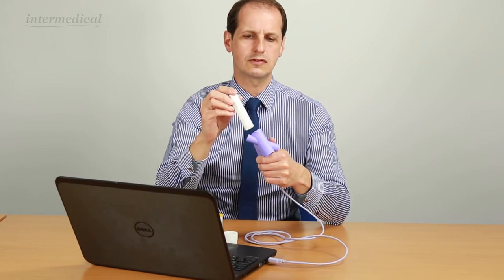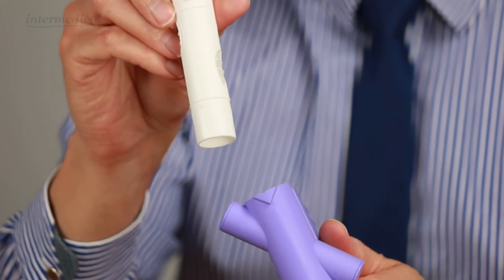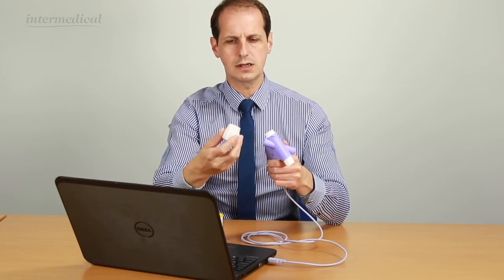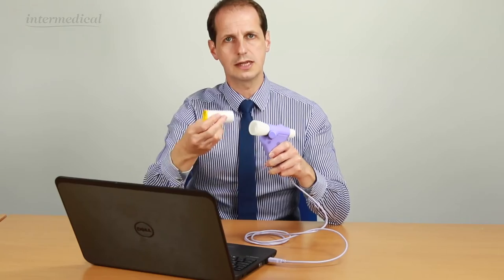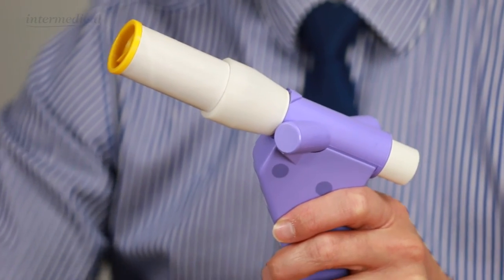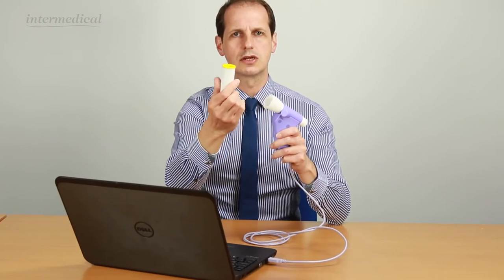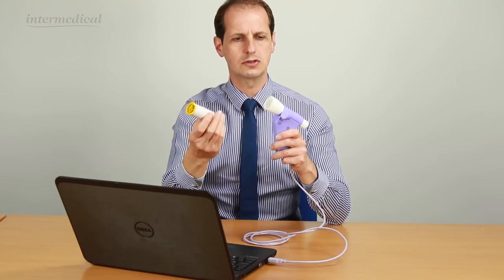To pop this in, you'll see there's a triangle on here and a triangle on the spirette M. Push that in. Then onto the front goes a mouthpiece adapter. And then your standard spirometry cardboard mouthpiece will just go onto the front of that. So between each patient, you obviously change the mouthpiece because they're single patient use, and the spirette M is changed on a weekly basis.